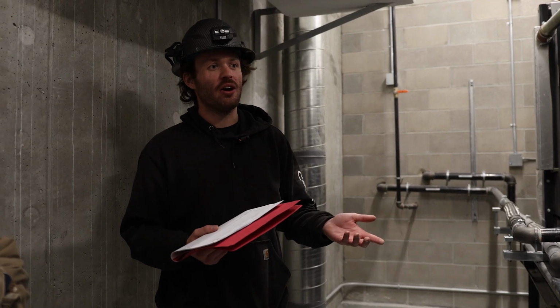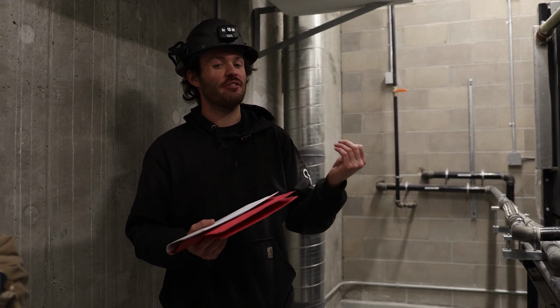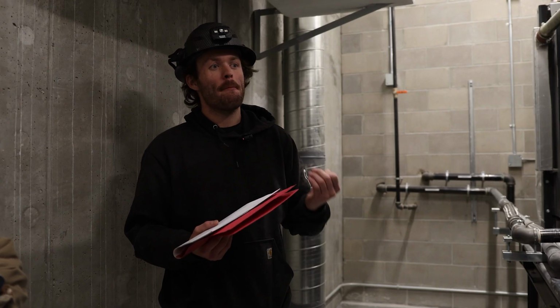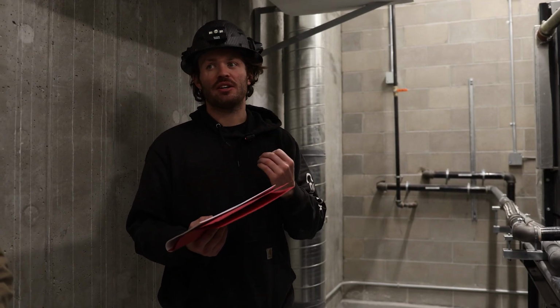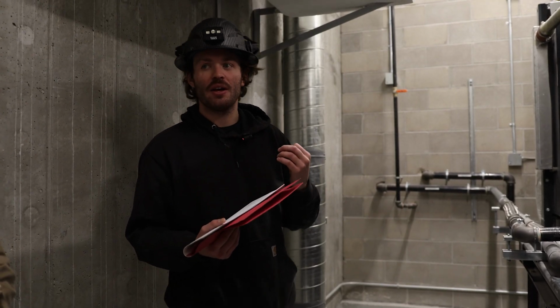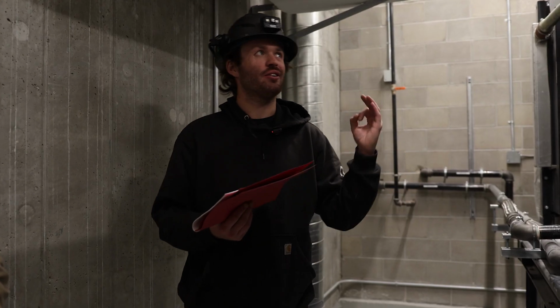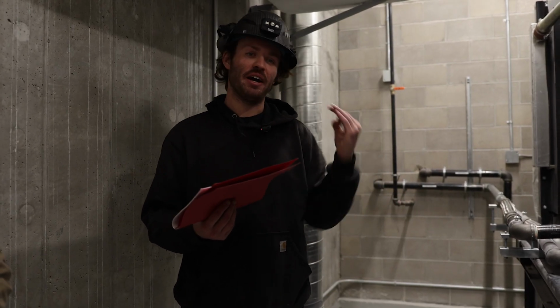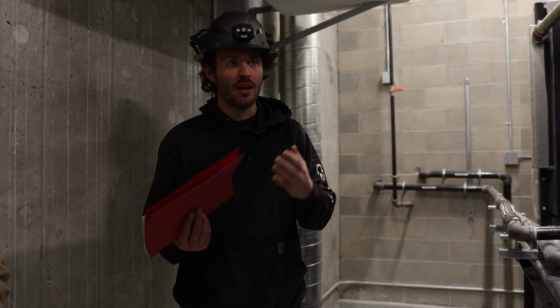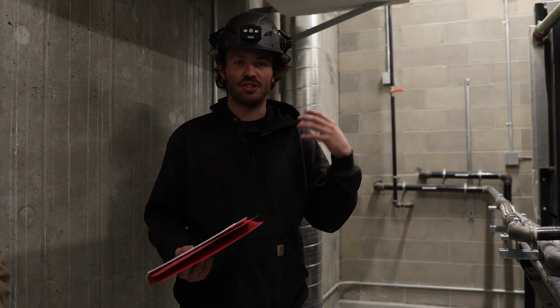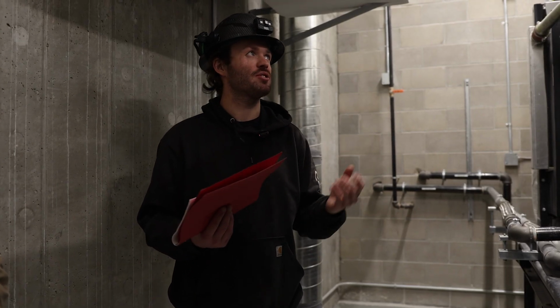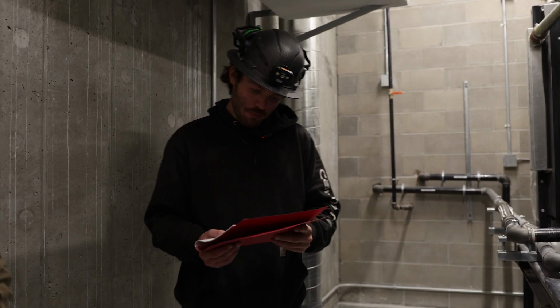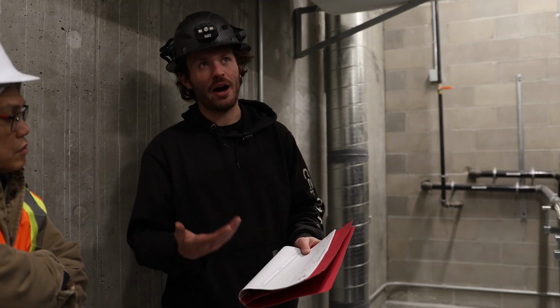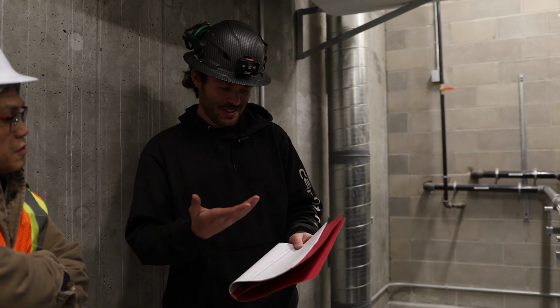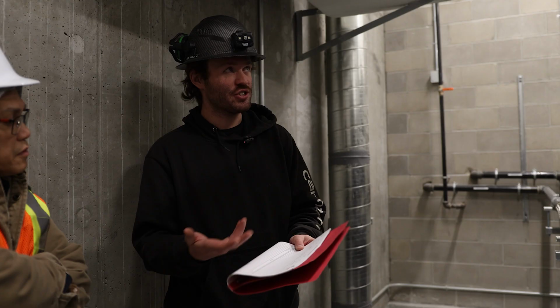Once the power comes back on, you'll still see that battery charger fault on there, but your battery charger will actually be charging. The fault will not clear until you flip the key to the off position and back into automatic. You won't have that happen on test. It'll just be any times the actual power fails to the building. Back to this. So how I got off on that tangent, pardon, is battery charger.